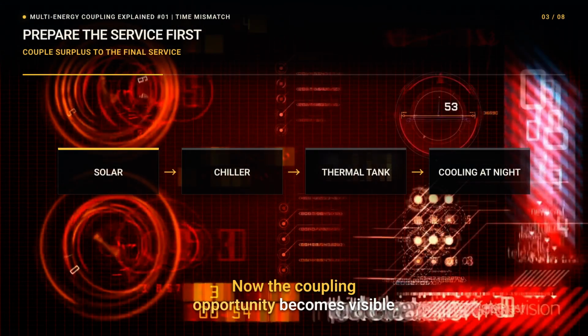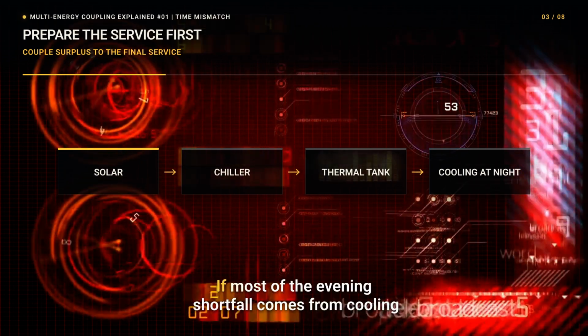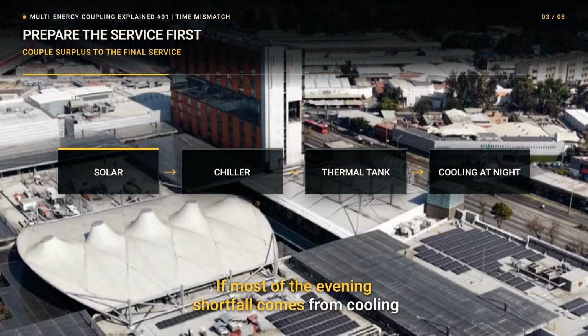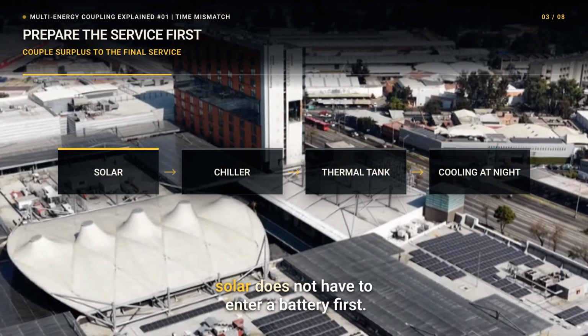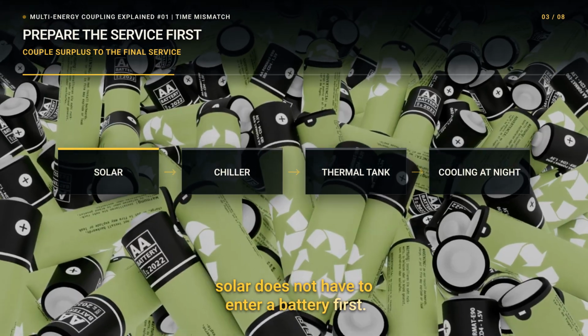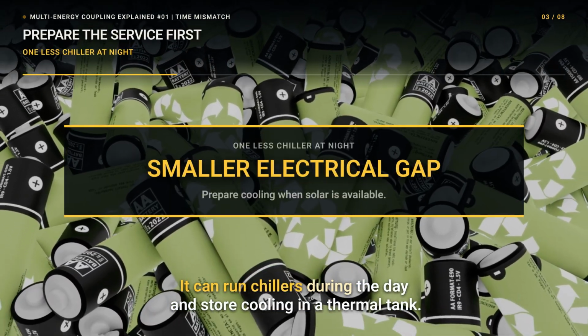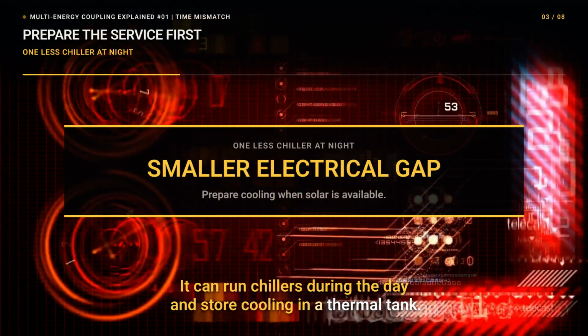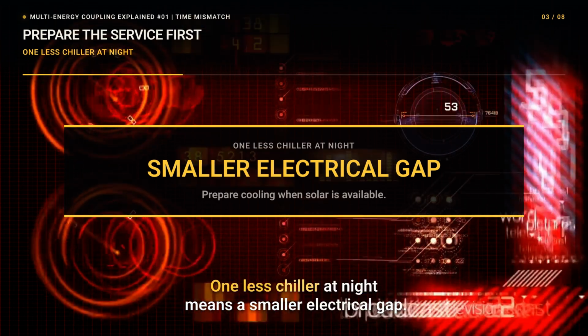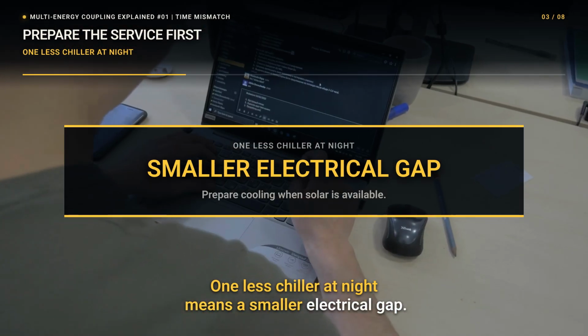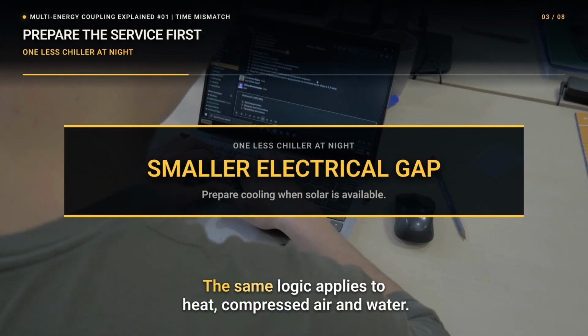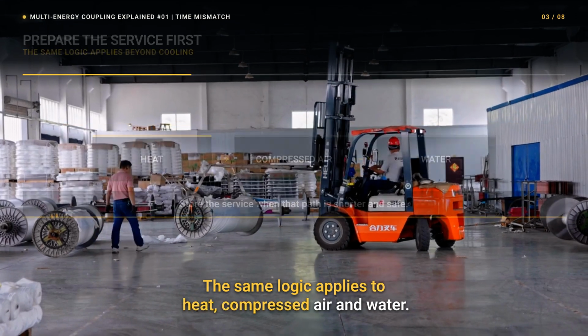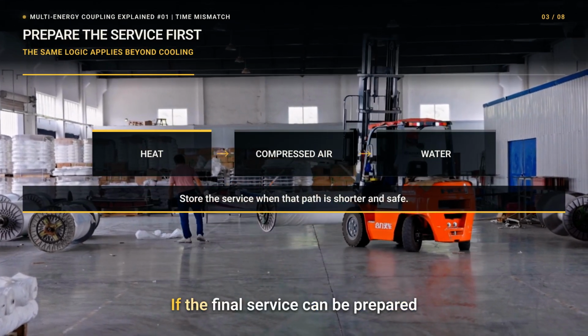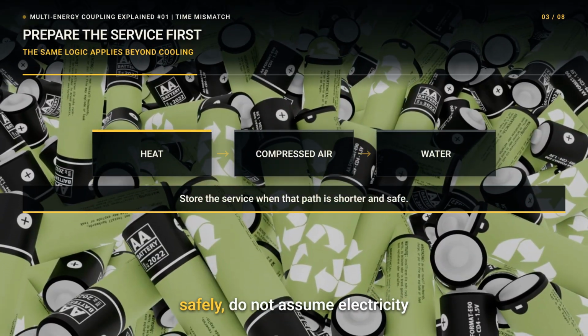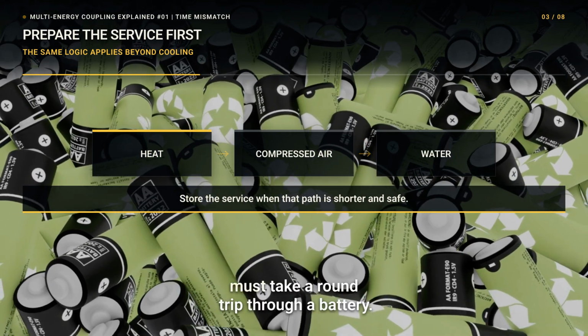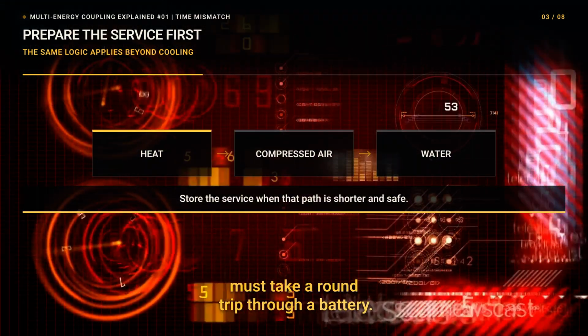Now the coupling opportunity becomes visible. If most of the evening shortfall comes from cooling, surplus solar does not have to enter a battery first. It can run chillers during the day and store cooling in a thermal tank. One less chiller at night means a smaller electrical gap. The same logic applies to heat, compressed air, and water. If the final service can be prepared safely, do not assume electricity must take a round trip through a battery.